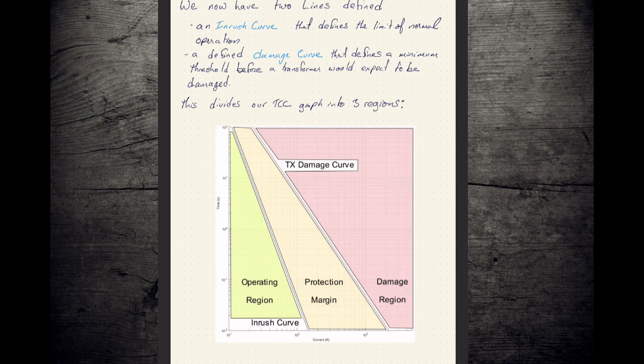So we end up with two lines. We get our inrush line, this is our normal region, and we get our transformer damage curve. You cross the curve, you've cooked your transformer. You don't cross the curve, it's expected your transformer is going to survive. Doesn't always happen. These things can't take an infinite number of hits right up against the edge of the line before they let go. But the expectation is, and for the purposes of our course and the development of fuse protection, as long as you stay under the damage curve line, the transformer should survive unharmed.